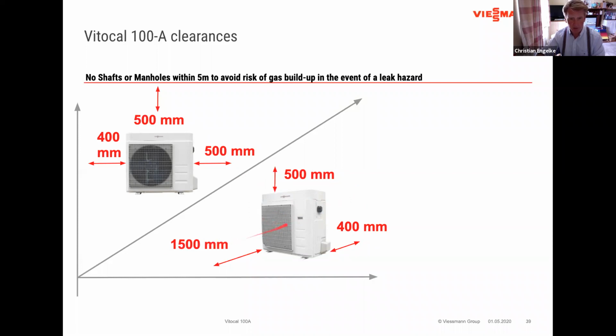And the same is true to the front. The air needs to be freely blown out to the front of it. So we need to provide a decent distance to the front. Also, because if you put plants or bricks, or the next building, right in front of the fan unit, you're creating potential damage to the fabric or to vegetation, because in the winter there are negative temperatures coming out of here, and you're creating some permafrost conditions, and that's not really desirable. But also obviously the fan performance suffers from it. So these are the minimum requirements.